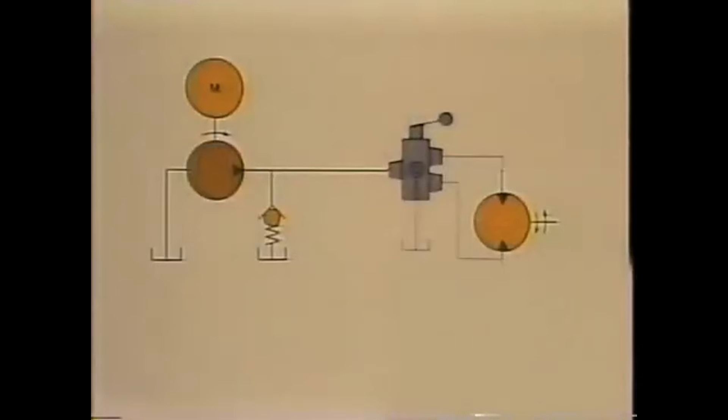Now that we've got a handle on a basic hydraulic circuit, let's try a little arithmetic. Let's assume the displacement of the pump is the same as the displacement of the motor. This means that in one revolution of the pump, there's enough fluid put out to drive the motor one revolution. With the electric motor driving the pump at 1200 RPM, the hydraulic motor would also run at 1200 RPM, neglecting a little internal leakage since nothing's perfect.